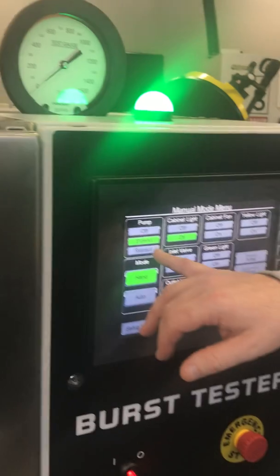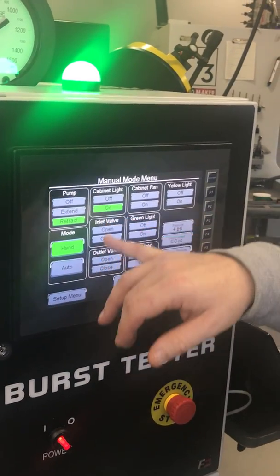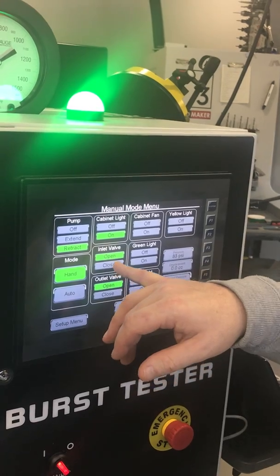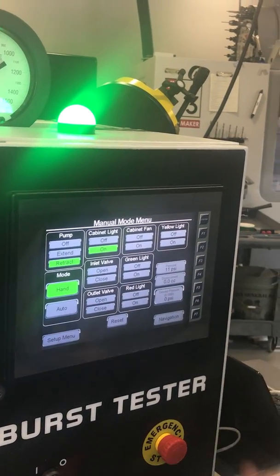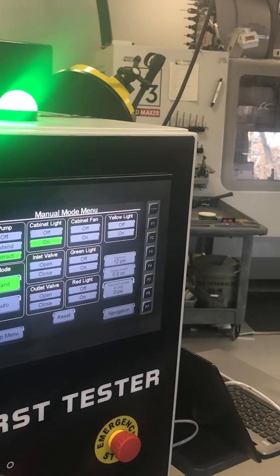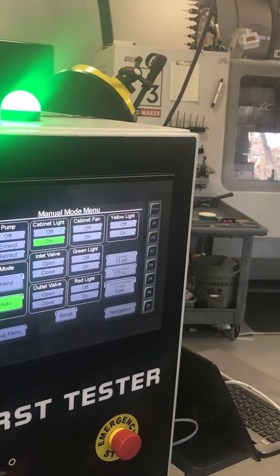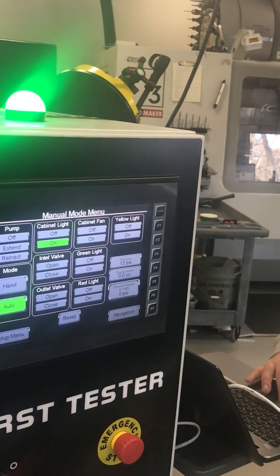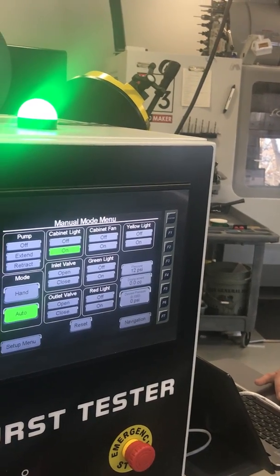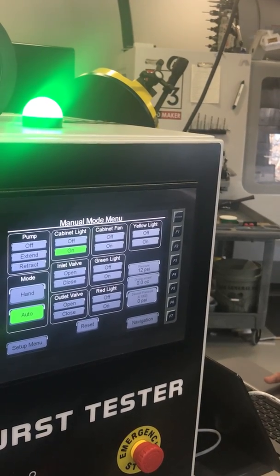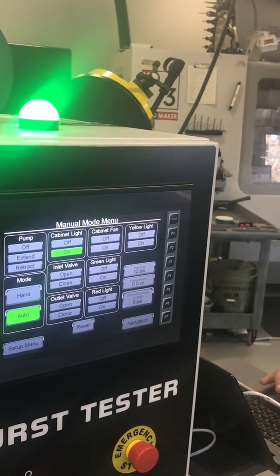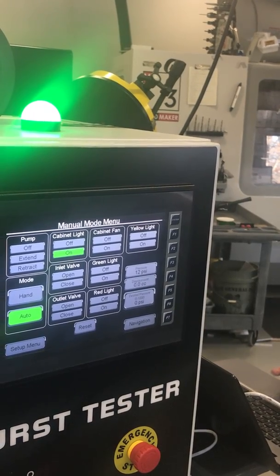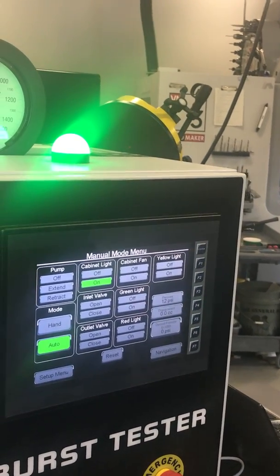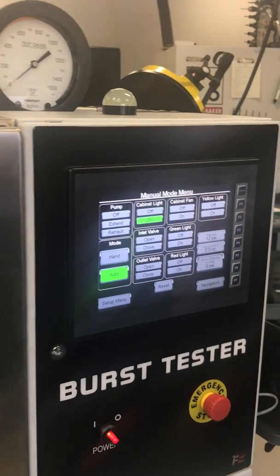0. Then you can retract the pump. Open the inlet, open the outlet. I think I already did that. At some point the displacement won't read 0. It's kind of like setting your calipers. But if you actually had your city water pressure tied in and the valve's open, it's being pushed down like your thumb, not really pushing for 0. So there's gonna be a small difference. When you calibrate this thing, you get your light to flash, right? And it'll be 0 at the start of your test.